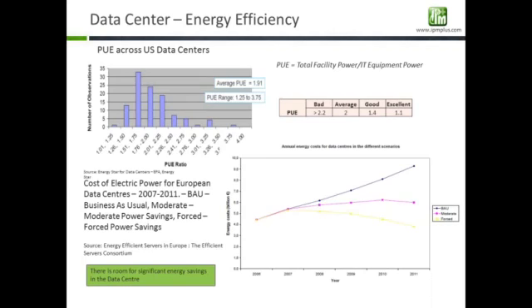It's very inefficient. If you look at the histogram of PUEs, the average PUE is around 1.91 across the US, though that's not representative of everything. You also see a lot of data centers in the range of 2 to 2.5 to 3, which is a matter of big concern because so much energy is getting wasted.